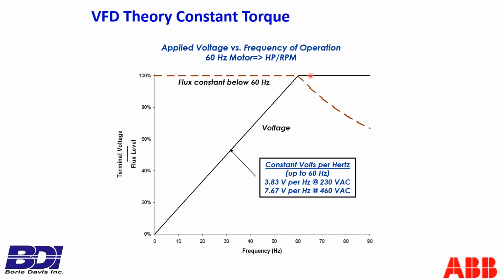If I go up to a higher speed, then what I really see is the bottom of this equation is increasing and the top is constant. I don't have any more voltage and current to give. So I'm what's called constant power. And when I'm constant power, the torque available is dropping off. And if the operating point were to go above that torque available, that motor would slip out and we'd be done. We wouldn't be able to run the application. So it's all engineered to stay down here when you go above 60 hertz, and that is a caution about going above 60 hertz.